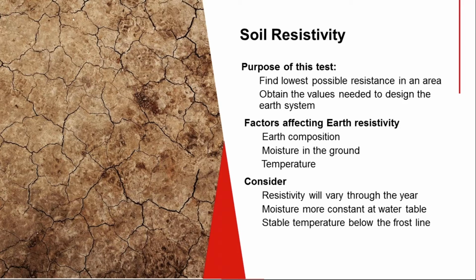Resistivity is based on numerous variables, of which earth composition, moisture in the ground, and temperature are all very important - I'll touch back on those from time to time. Certain types of soil, like loam, are pretty good grounding materials with good electrical continuity through the soil. Other types, like sand, are pretty bad. So if you're in a sandy environment, you're going to have more of a challenge getting a good ground than somebody up in the Iowa farmland or someplace like that.